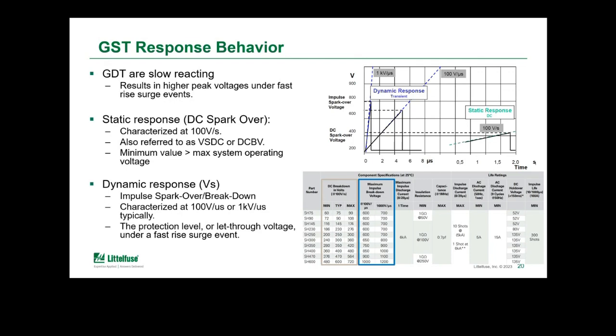Now, the response time is a key thing to take into consideration when you're looking at GDTs, and this breaks down into two different states. The first one is the static response state, which is typically characterized using a 100 volt per second rise time waveform. This is also referred to as the DC breakdown voltage, or DCBV, or VSDC. When you're selecting this device, the minimum value of this DCBV needs to be greater than the maximum operating voltage of the system. Otherwise, there's a potential for a false trigger.